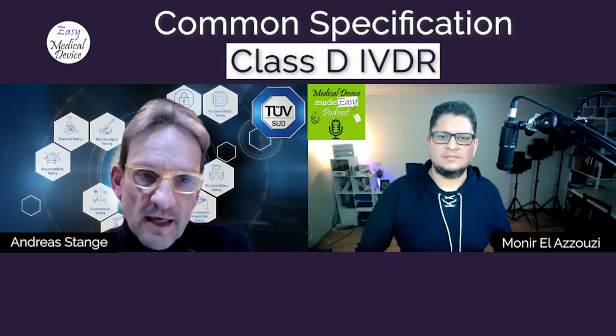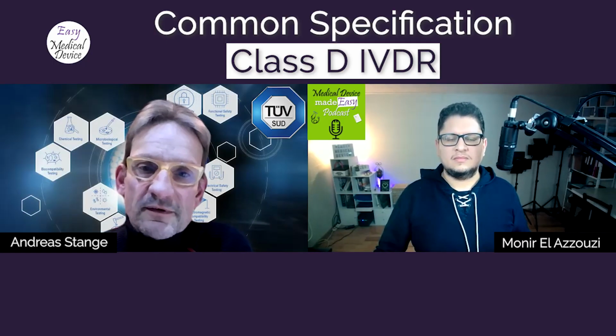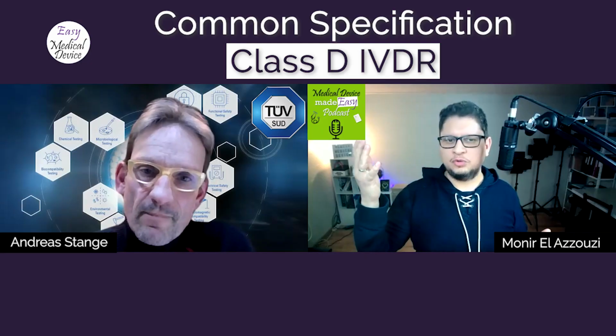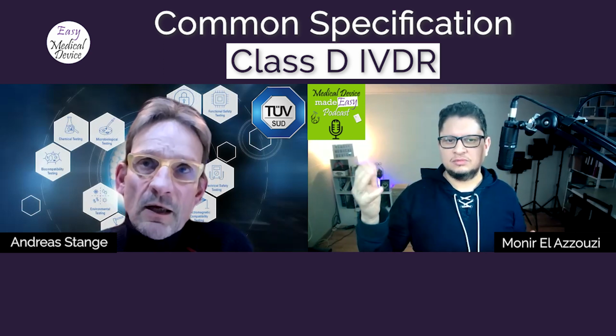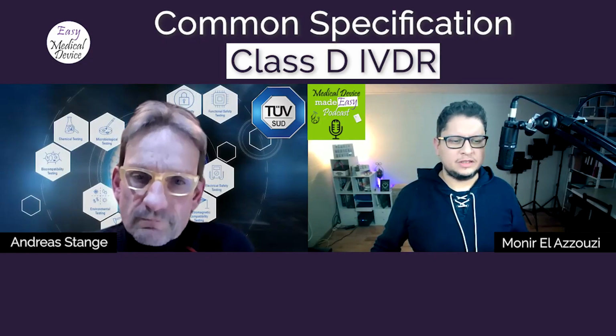But the notified body will, of course, seriously question the device if it's not coming close to these values. Okay, and if notified body sees that we are not following those common specifications, they have to go through the expert panel, I suppose, also. I don't know. No, the expert panel is not necessary anymore. No? Okay. This is just a discussion between notified body and the manufacturer, and that needs to be sorted out. Okay, then it's good then.